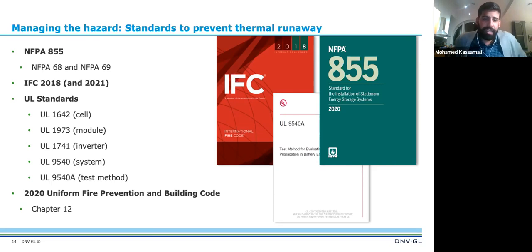UL 9540A testing is currently in its 4th edition, and it's been a learning process in how to accurately and properly test these battery cells. This 4th edition, which came out last year, has gone a great length to help prove whether or not your battery cell is a safe design. This test is done at the cell level, the module level, and also at the unit and installation level. The unit is defined as either the battery rack or an enclosure, such as a cabinet style energy storage system.